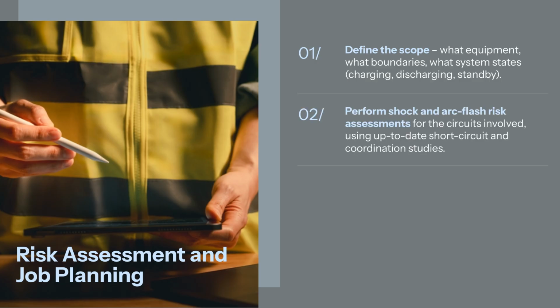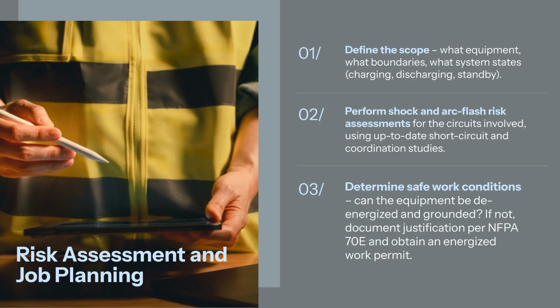2. Perform shock and arc flash risk assessments for the circuits involved. This must be performed using up-to-date short circuit and coordination studies. 3. Determine safe work conditions. Can the equipment be de-energized and grounded? If not, you must document justification per NFPA 70E for why the system cannot be placed in an electrically safe work condition and obtain an energized electrical work permit.